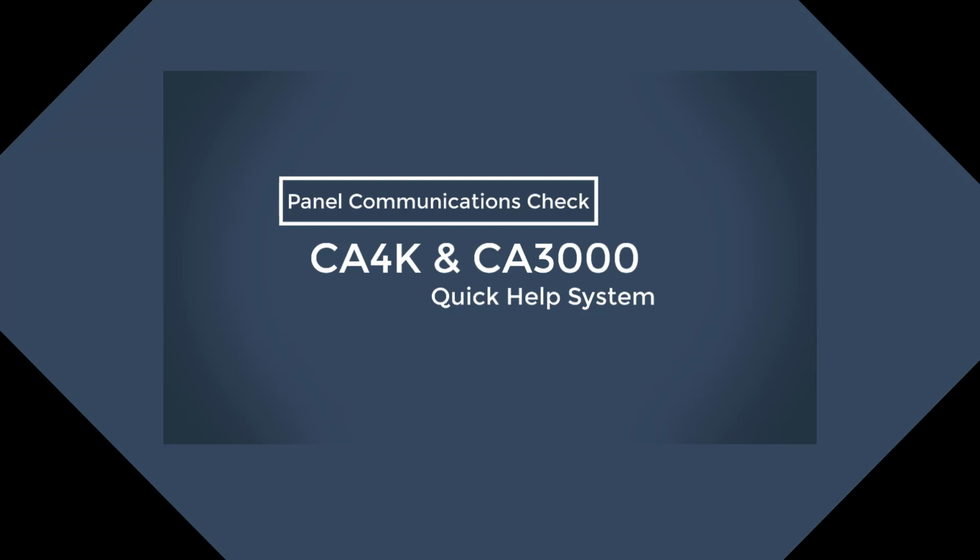First, you would check the network settings at the panel. You must verify the IP address of the panel has not changed. That is why it's recommended to use a static IP address. Next, you would check under Communication COM ports, also known as channels, in the CA4K. The IP address configured in the COM port channel screen must match the IP address programmed at the panel.